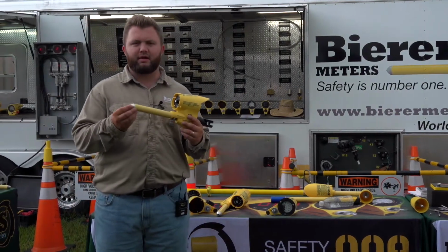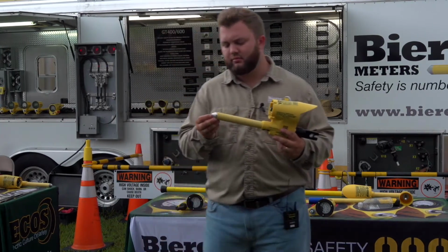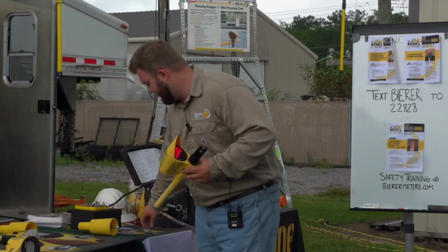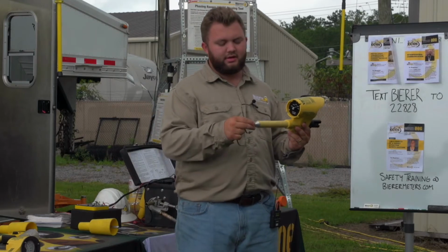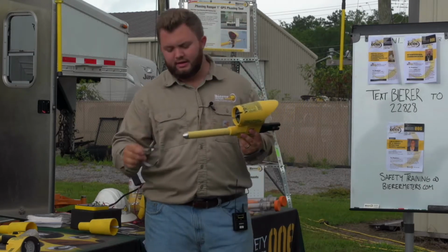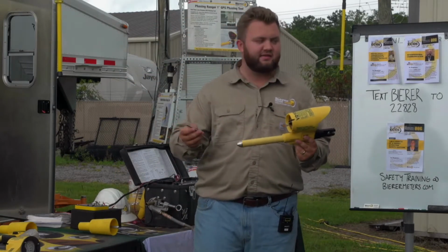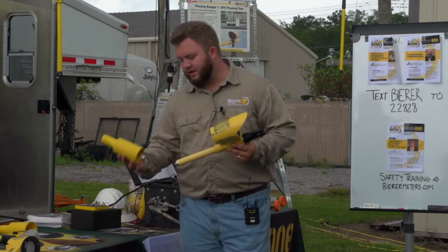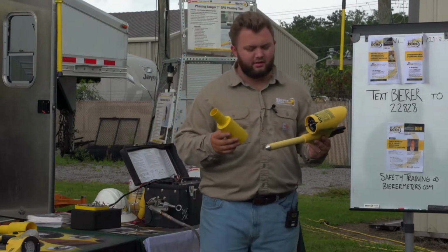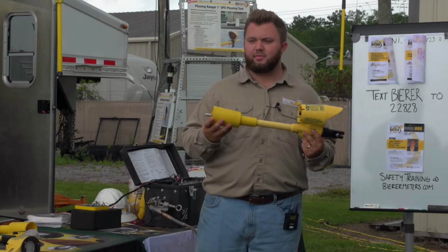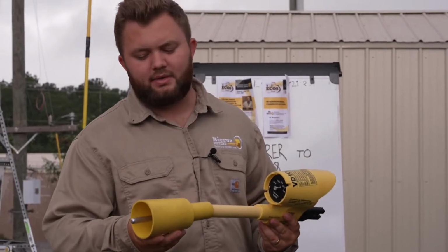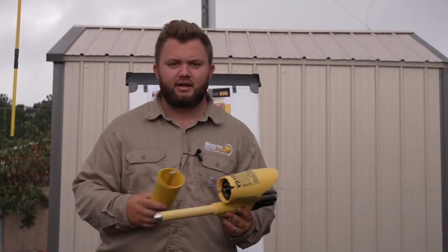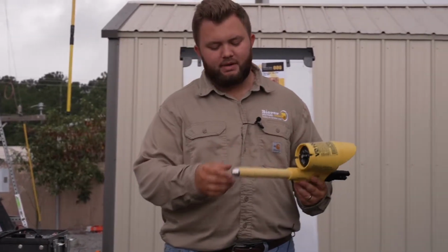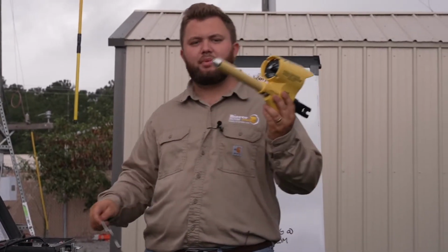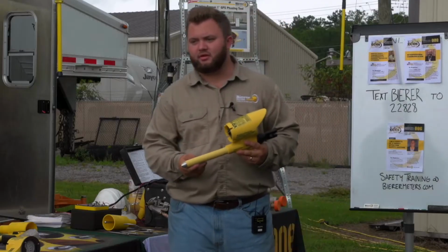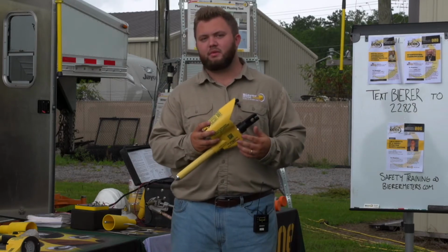Also, what we recommend is always using an adapter on the end of the probe. So we have our live line fittings that go on the end of the device. Those accessories extend out from the device: a hook probe maybe if you're using it on an overhead conductor, a straight probe if you're using it maybe at a point source like a capacitive test point, or we've got the bushing adapters for underground, and also elbow adapters for underground. You put it on the end of the tool, and it helps extend out and helps with your depth perception. That way you're not bypassing that line limiting mark with an energized source or a ground. Maybe overhead you're using a hook probe, that way you don't bypass the conductor, bypass that line limiting mark. It just helps your depth perception for proper work methods.